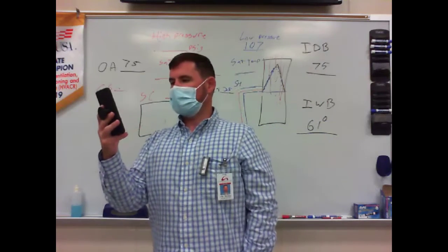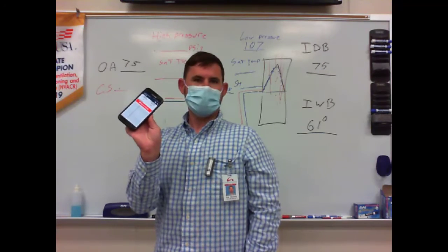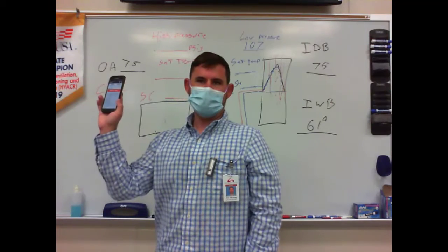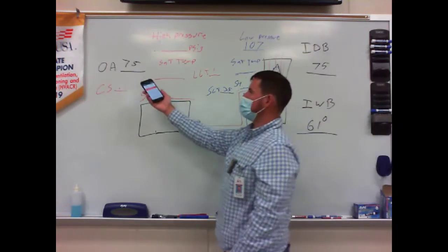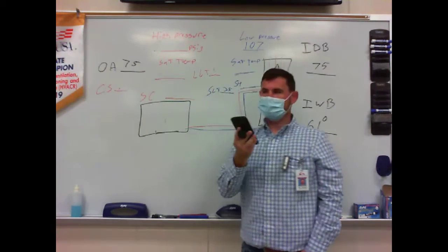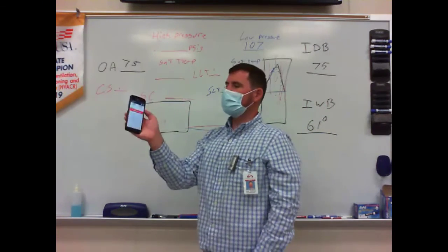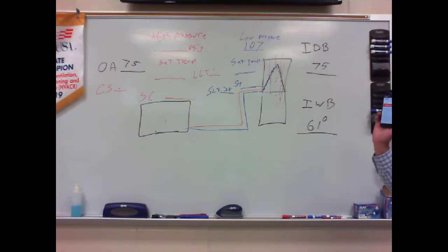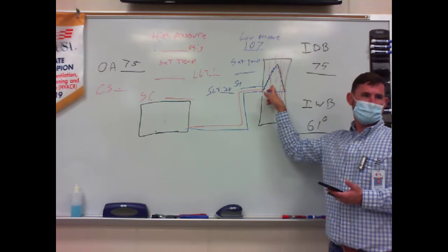Once I calculate that, it says my current superheat is 0 degrees. It says my recommended superheat is 15 degrees. The outdoor ambient temperature was 75. This is 410A, yes. So according to this, my recommended superheat was 15 degrees, but I have 0 degrees. If I have 0 degrees superheat, is that evaporator starved or flooded? Or normal?